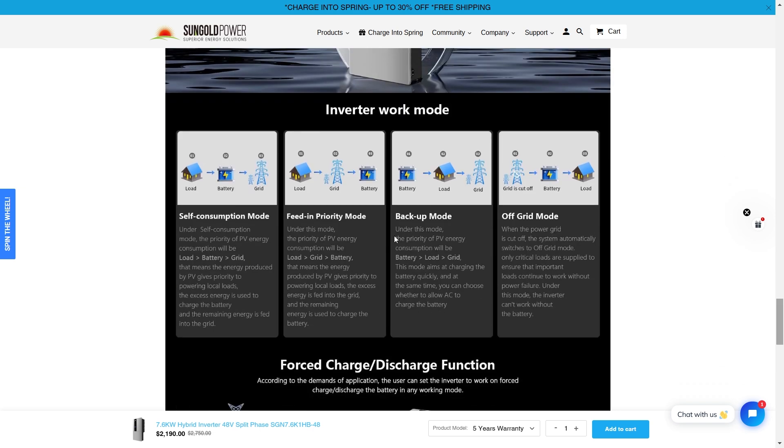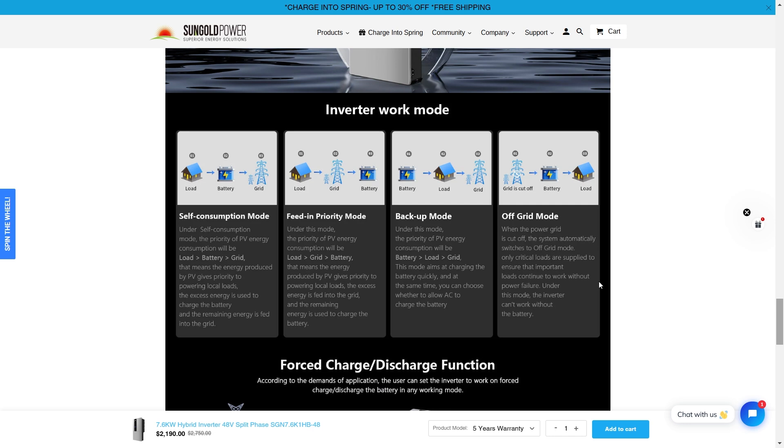So these are the different inverter work modes. You got self-consumption mode. Under self-consumption mode, the priority of the PV energy consumption will be load, then battery, then the grid. In feed-in priority mode, it goes from load to grid, then the battery. In backup mode, it'll go from battery, load, then the grid. In off-grid mode, it will only power critical loads that are supplied to ensure that important loads continue to work without power failure. Under this mode, the inverter can't work without the battery.